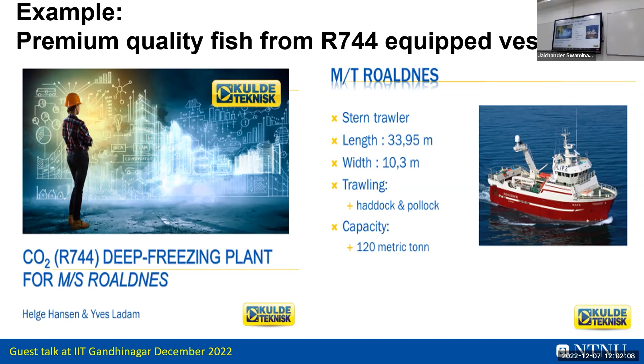This is an example on a small fishing boat in Norway. They had previously R22, as you have in this country also. This was the R22 system. Inside the same space, they put the CO2 system, and they could implement even a bit more capacity because it's more compact. What happened is they could freeze more tons per day fish, and it was faster. These plate freezers were faster because they can go lower on temperature.